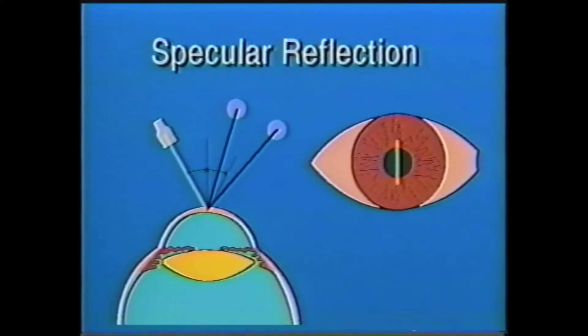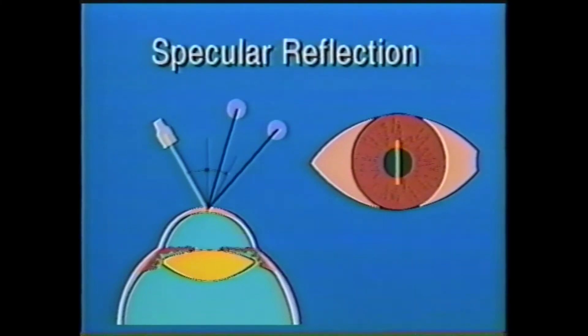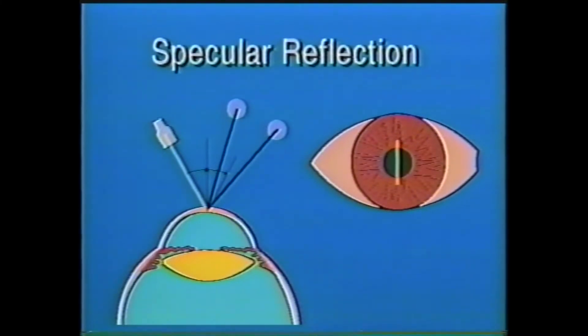Fifth, specular reflection. This reveals details that are seen when the reflected light is viewed at the same angle from the perpendicular as the angle of incidence of the slit beam light. This type of illumination is ideal for examining the corneal endothelium.